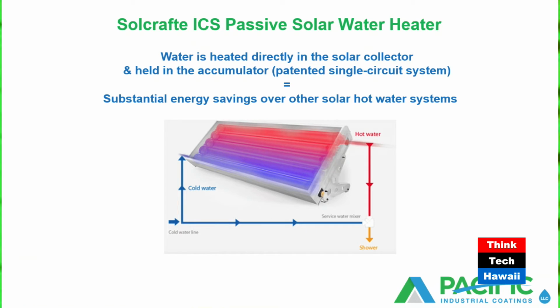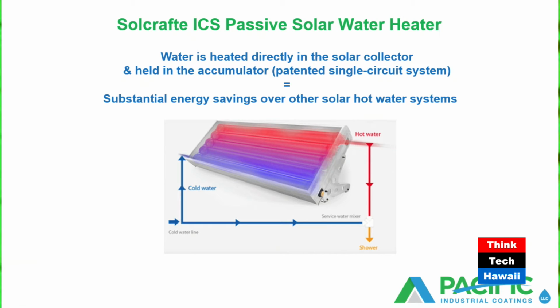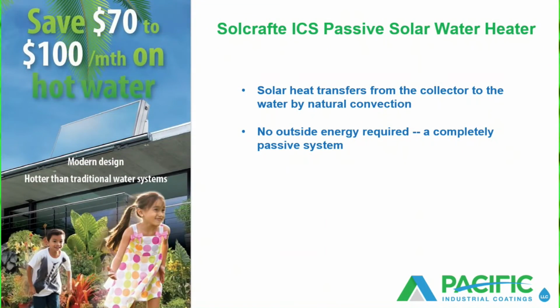And this next slide really shows well what it looks like, the water being fed into the collector, building heat and coming down hot. Again, it's going to be stored quite a bit hotter because you don't need what you described earlier as a differential controller between the tank temperature and the collector temperature. In a traditional system, whenever they vary by 12 degrees, that pump is told to start and it takes the water and transfers the heat from the collector down into the tank. When they get within 4 degrees of each other, the pump is told to stop. So they have a handshaking that goes on and off throughout a period of time to bring the temperature up to about 120. In our system, this particular tank can go quite a bit higher than 120. So you're bringing that down into your lower tank and heating that up very quickly, and not needing to use your backup system as often.